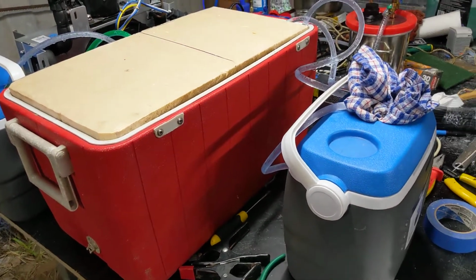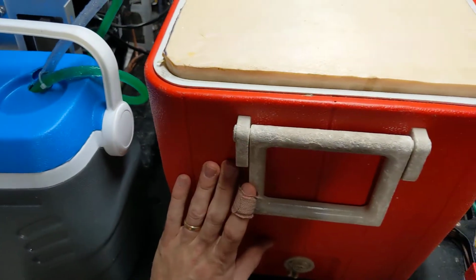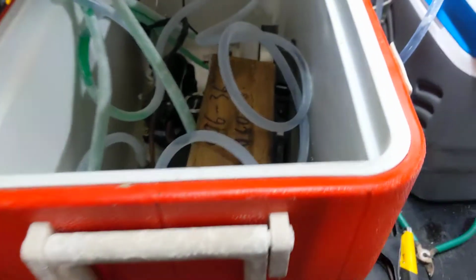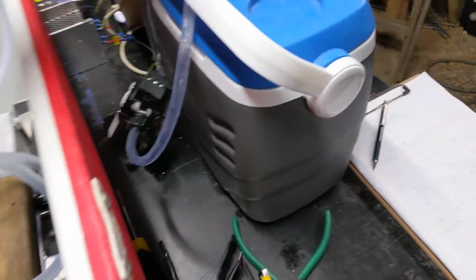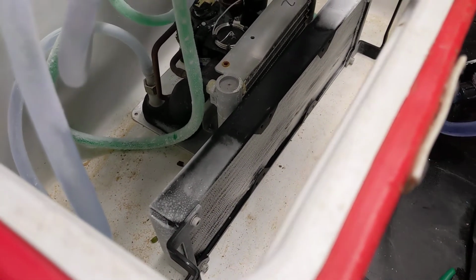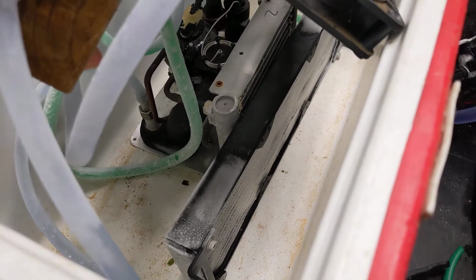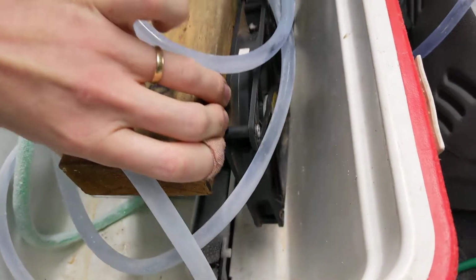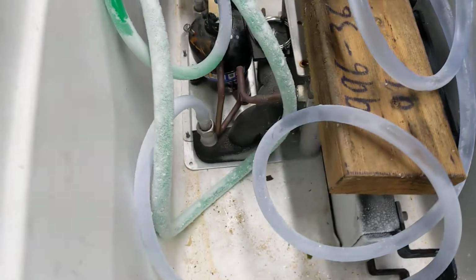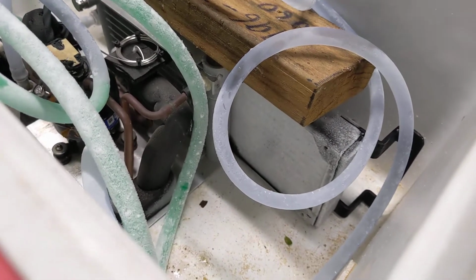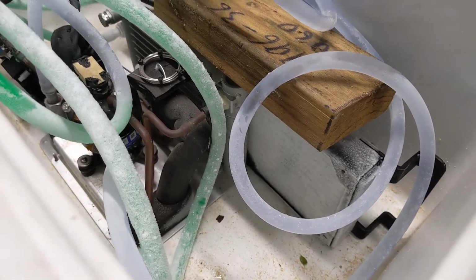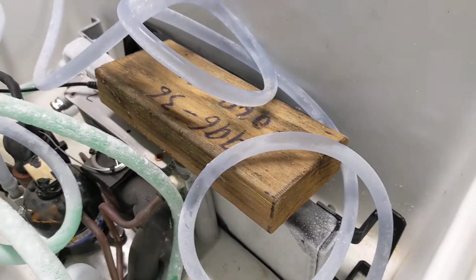So if you're fridgy minded, you've probably already worked out what the problem is, given this is at -13 and the air in here is at +4. My radiator has completely iced up, so my esky is not sufficiently protecting it from atmospheric moisture. It basically just stopped doing the job, stopped exchanging coolth, and has frozen solid. The glycol is still liquid, so it was still flowing through it, but there's no capacity for air to flow through that radiator.